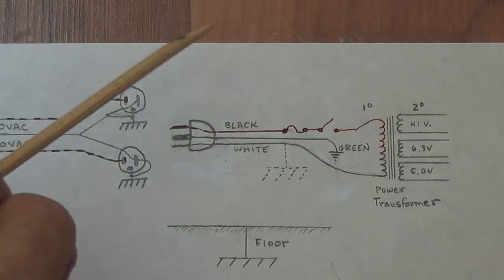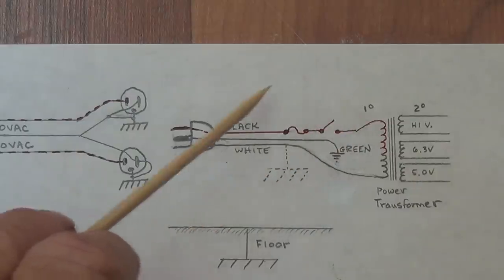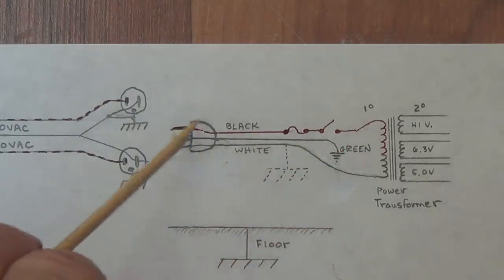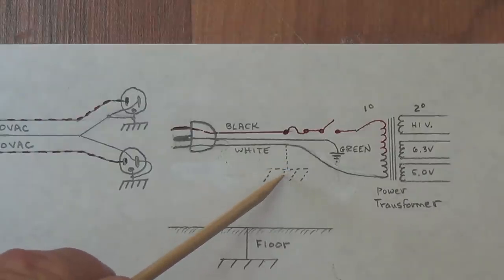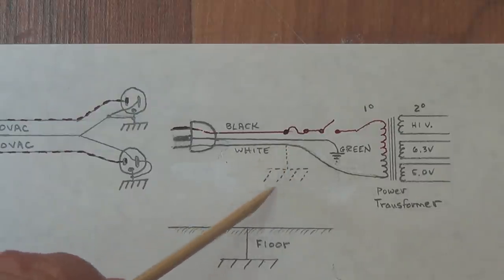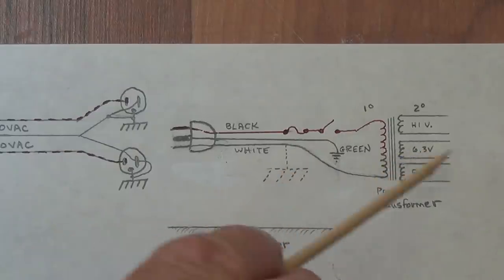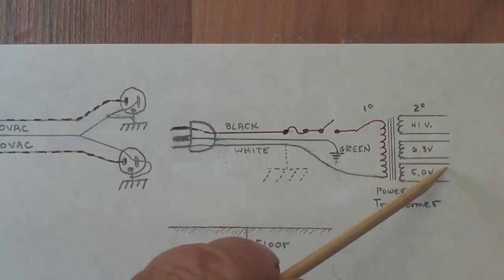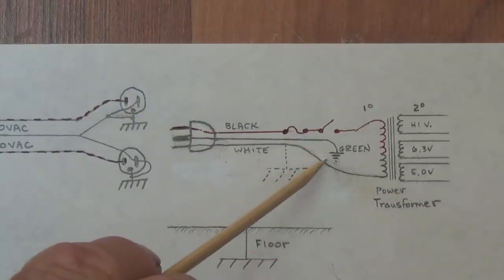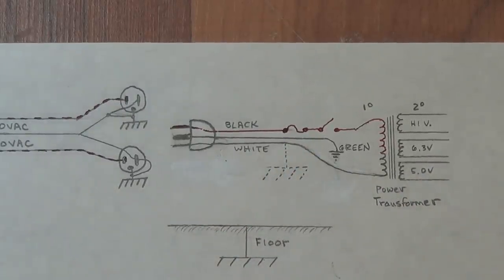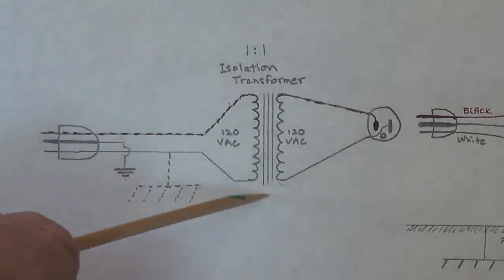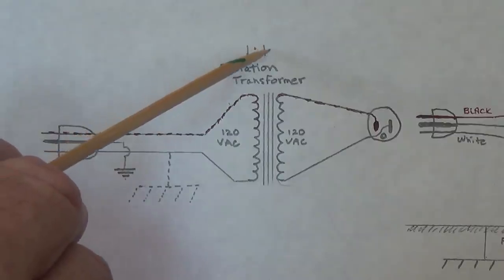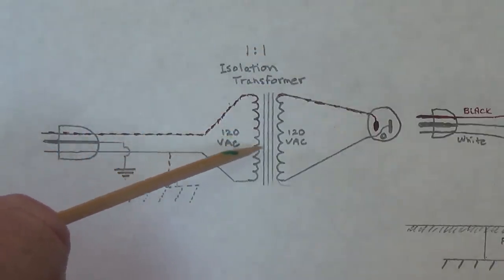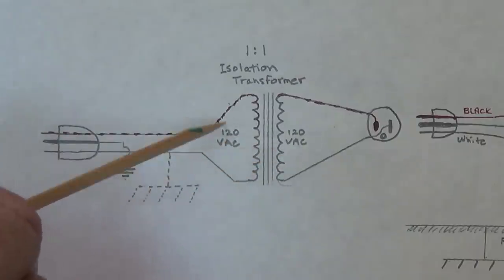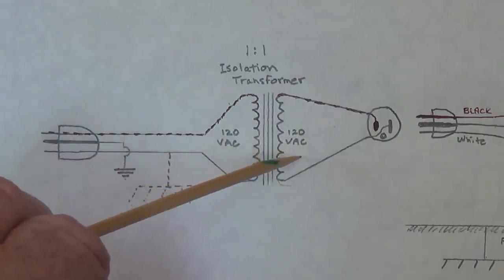Now, what if we could magically change this somewhat dangerous primary side of the circuit and eliminate this earth grounding that it has here? If we could eliminate that, then both sides would be as safe as the secondary side is already. And the way that we can do this is with an isolation transformer. Okay, here is our isolation transformer. It's generally a 1-to-1 winding ratio because we don't want to step up the voltage or step it down. We want it 120 volts AC on both sides.